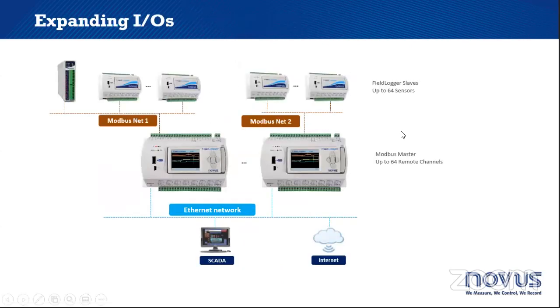Expanding IOs, this is that possibility I mentioned before. You will reach out to us and say, oh, Bruno, I want 12 channels or 15 channels or something like that, but the field logger only has 8. Well, why not expand it? Use the Modbus RTU network to expand its possibilities.